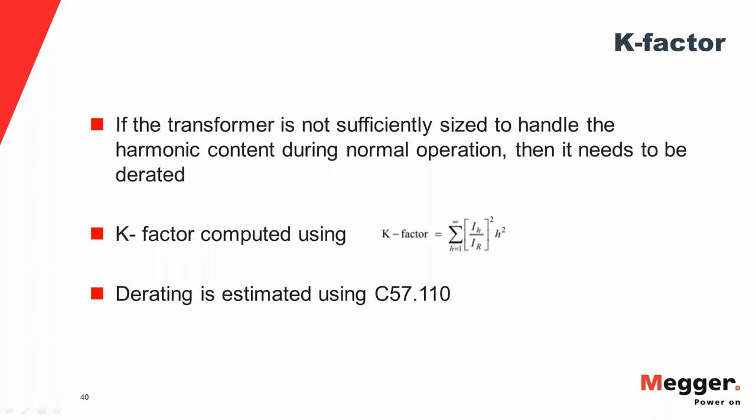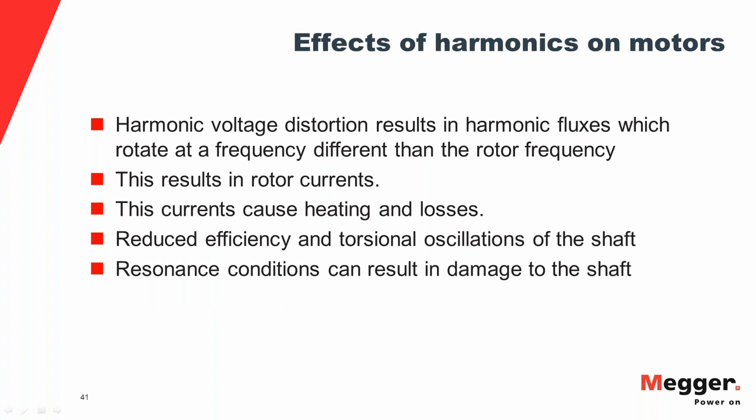Effects of harmonics on motors: harmonic voltages result in harmonic fluxes that rotate at frequencies different from the rotor frequency, which operates near the fundamental frequency. The interaction between these fluxes and conductors induces currents that cause heating and losses. Additionally, the interaction between currents and the field produces pulsating torque, causing oscillations on the shaft. If the frequency of these pulsations matches the natural frequency of the shaft, mechanical resonance can occur, amplifying the oscillations and potentially damaging the shaft.